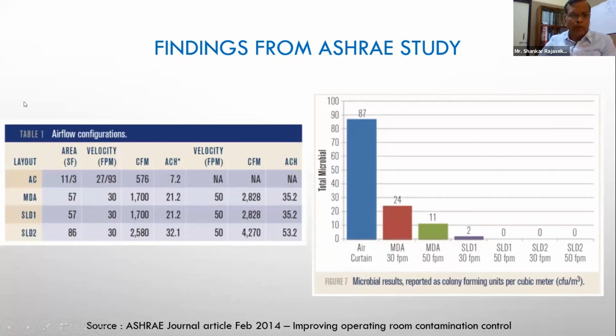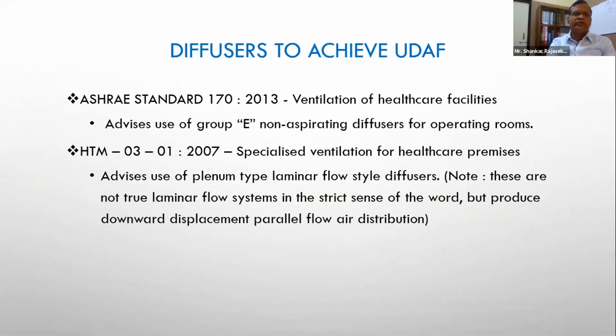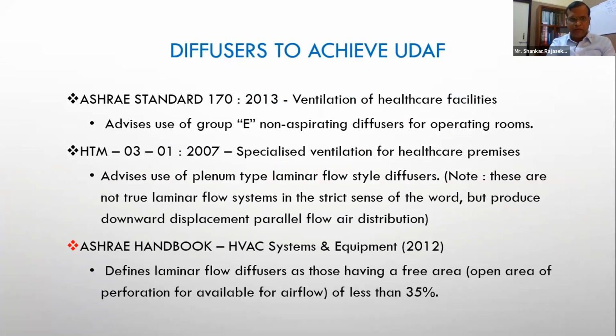And most of the theaters nowadays have an 8x8, which is 64 square feet, or they have 8x6, which is 48 square feet, pretty much close to this, I would say. So if you operate it anywhere above 30 feet per minute, we are likely to get very low microbial CFUs per meter cube on the operating table, thereby the aseptic nature and the sterility of the air will be maintained. So I'm giving some information about how to achieve this unidirectional airflow and what diffusers to use. I'm not going to be reading through it. It's quite self-explanatory in nature.